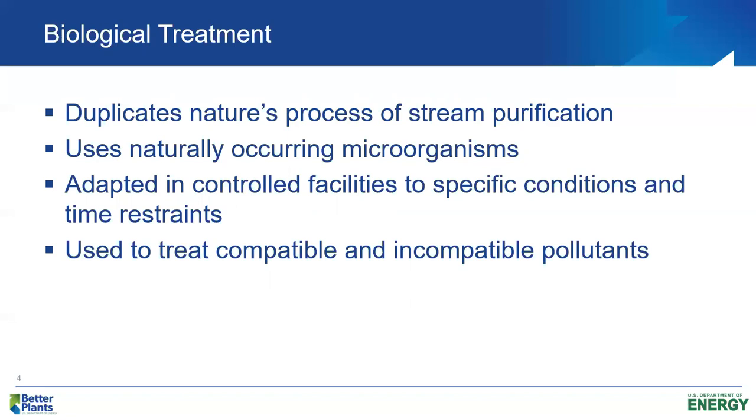We're going to use naturally occurring microorganisms. These are basically soil microorganisms. And we're going to use controlled facilities wherein we'll have a certain temperature, pH, dissolved oxygen concentration, and ORP, oxidation reduction potential value. These are environmental conditions that will significantly impact the functioning of the microorganisms. And then we have time restraints that we have to deal with. We may design a biological reactor for a 1-hour detention time or it may be designed for a 24-hour detention time. And so we have to deal with those constraints that we have in the treatment process.